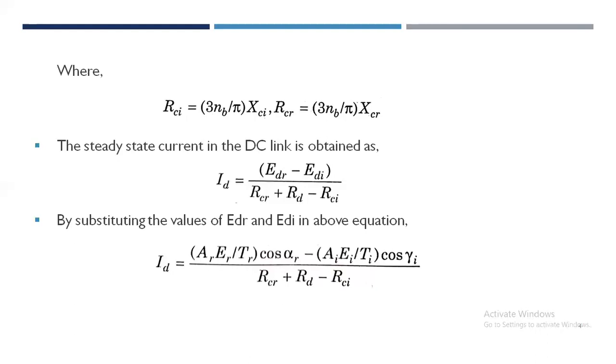As mentioned in the beginning, it is desirable to control the current and regulate the voltage simultaneously in the link. The question that can be posed now is which terminal should be assigned the task of current control while the other terminal regulates the DC voltage. From considerations given below, it is desirable to have current control at the rectifier station under normal conditions.